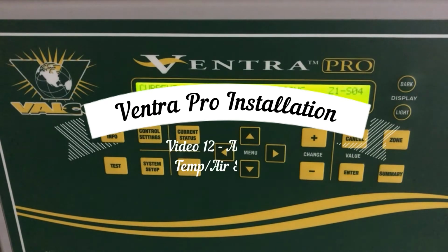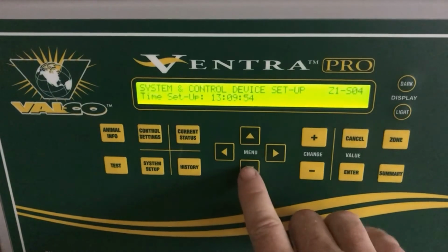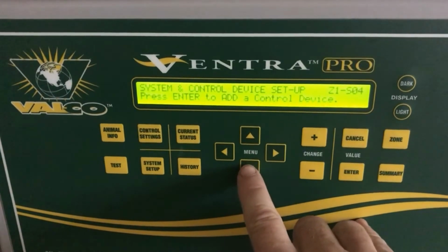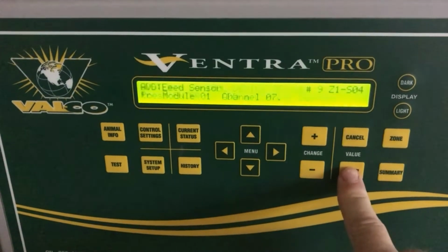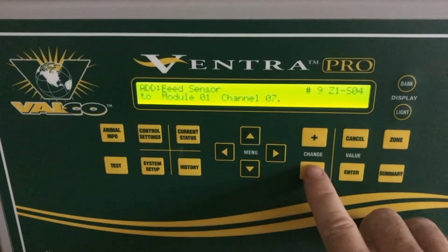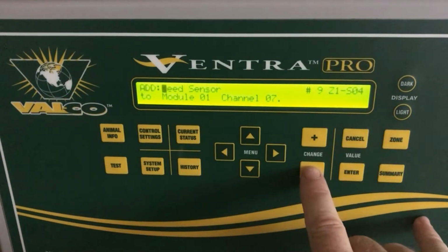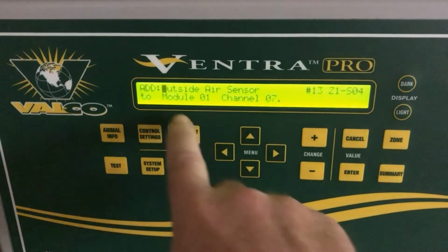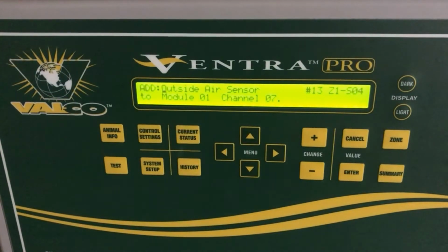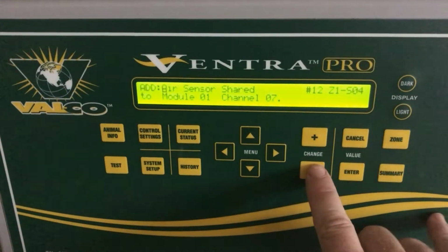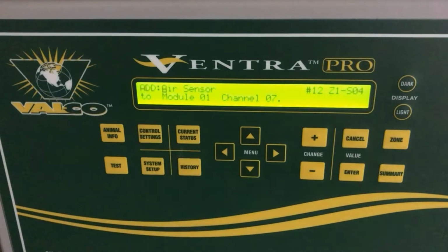This Ventra Pro video is how to install a temperature air sensor. First, we go to System Setup, menu arrow down, and press Enter to add a control device. Once here, you will scroll through your list and look for air sensor. Here is an outside air sensor, which is what you would choose if you wanted to add an outdoor temperature sensor. We continue to scroll, and there is air sensor.